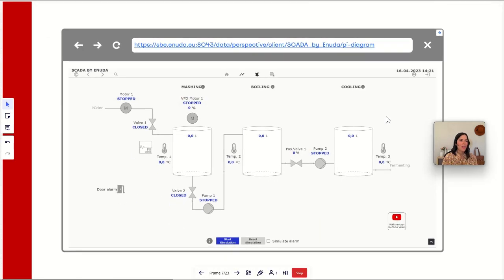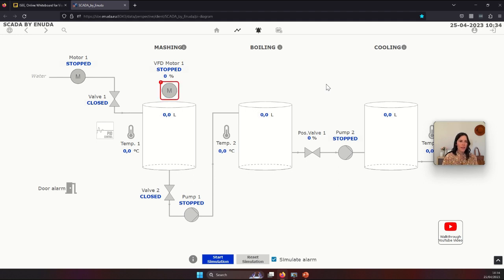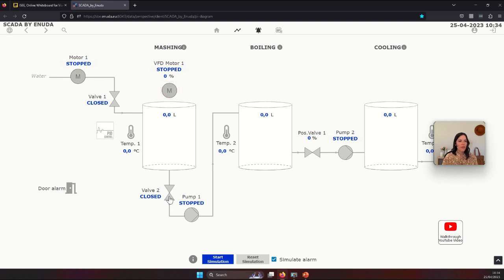That's why today I want to show you this solution. Let's take this as a high performance HMI. Here we have a demo of a brewing process for a high performance HMI. As you can see on the screen, we have descriptions with process values in bold blue. We also have some symbols to indicate components, so we don't have decorative graphics anymore. You can see that there is a red frame here to indicate that this motor has an alarm. All in all, this HMI will be very easy to understand for the operator.